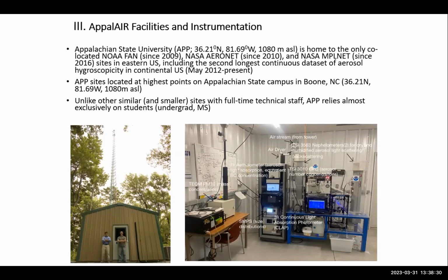In the event that others are interested in using the data. Each one has many sensors, so I'm not going to get into the sensors of each. But the air comes in here, and this instrument here and down here is called an aerosol scanning mobility particle sizer, which measures all of the diameters of the different particles. This is what's called an aethalometer. This right here measures black carbon concentrations and the spectral light absorption of aerosols.